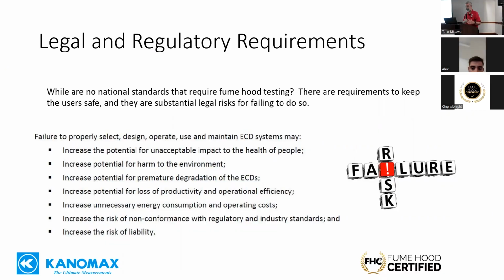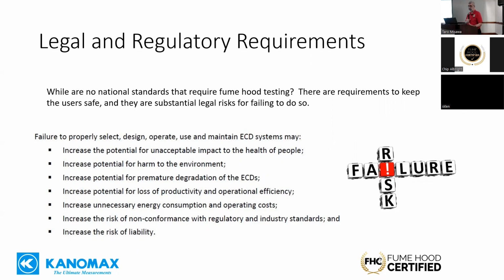And then we have the legal and regulatory requirements. You would think, as hazardous as hoods really are, there would be a requirement or a standard to test them, but there isn't. The closest thing we come to a requirement would be some of the OSHA guidelines. But what happens when you fail to properly select, design, use, and maintain an exposure control device? It increases the potential of unacceptable impacts to people's health. It increases the potential to harm the environment. It increases the potential for premature degradation of lab equipment and loss of productivity, et cetera, increases energy consumption and operating costs, and it puts you at risk of non-compliance and liability.